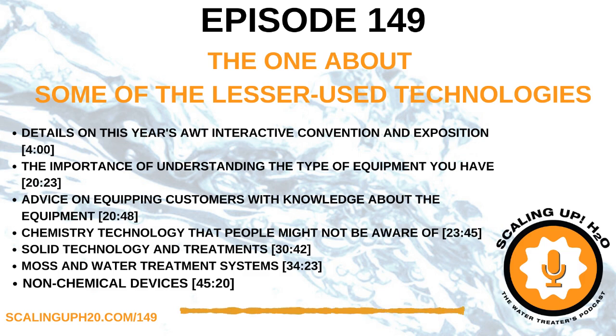And you may say, well, 2.2 is much lower than what we would ever see before. But because you're lowering your LSI, you're increasing the solubility of water. A lot of times you can increase the concentration ratio of the tower. So just by pulling those minerals out of the water, you're getting what you want from the system.